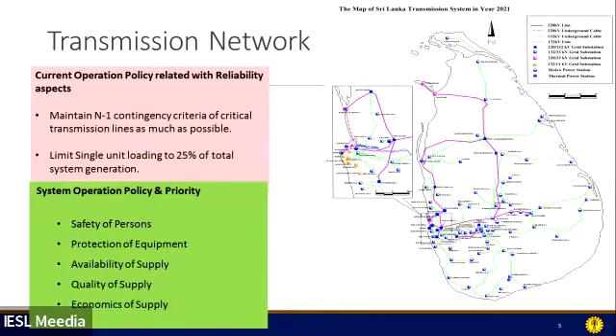At the same time, we limit a single unit loading to 25% of the total generation. This policy is basically related to reliability aspects. Then the general policy and priority of system operation: when we operate the system, we ensure the safety of persons, the protection of equipment, then the availability of supply, then quality of supply, and finally comes economy of supply. Now, based on the current situation, we have to look into those things.